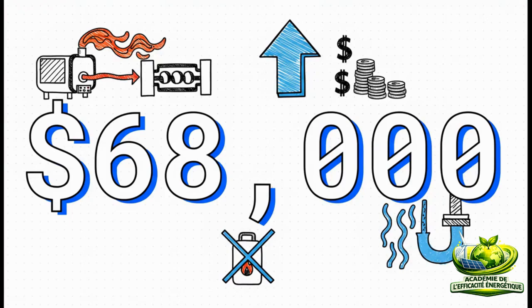And the payback? It's huge. Let's say you're running a continuous blowdown rate of 3,200 pounds per hour. You install a heat exchanger, and you recover about 90% of those energy losses. In a plant paying, say, $8 per million BTU for fuel, getting that heat back translates to a massive $68,000 in annual savings.